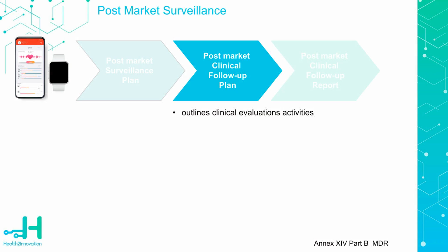Next, we have the Post-Market Clinical Follow-up Plan, or PMCF. This document is described in Annex 14, Part B of MDR to outline ongoing clinical evaluation activities to monitor the device's performance and safety in the real world.